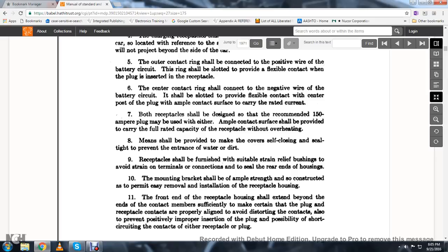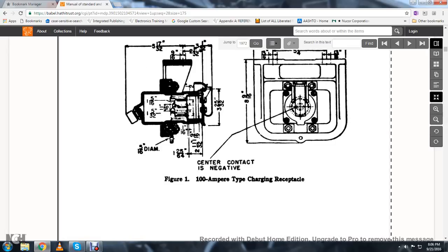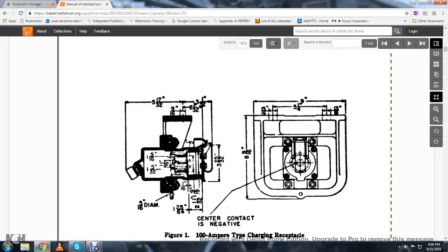Means provided for making the covers self-closing and seal tight shall prevent the entrance of water and dirt. Receptacles shall be furnished with suitable strain relief bushings to avoid strain on terminal connections at the rear end of the housing. The mounting bracket shall be of sufficient strength and constructed to permit easy removal and installation of the receptacle housing. The front end of the receptacle housing should extend beyond the contact points sufficiently to ensure proper alignment when inserting the plug, avoiding distortion of contacts and preventing improper insertion or short-circuiting.